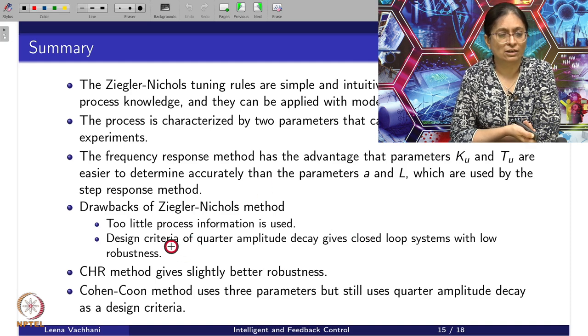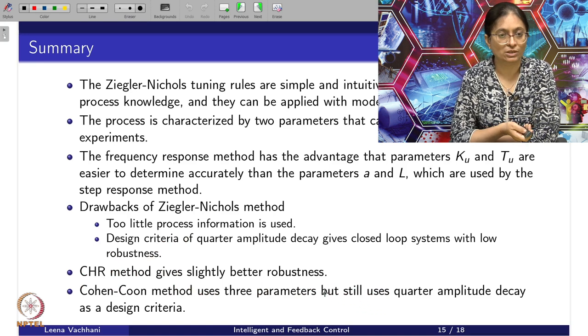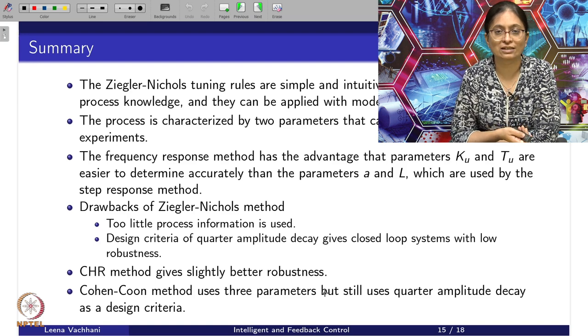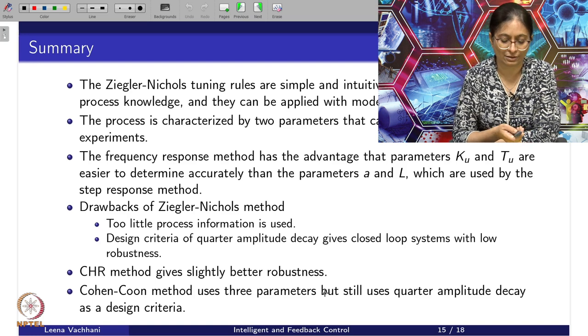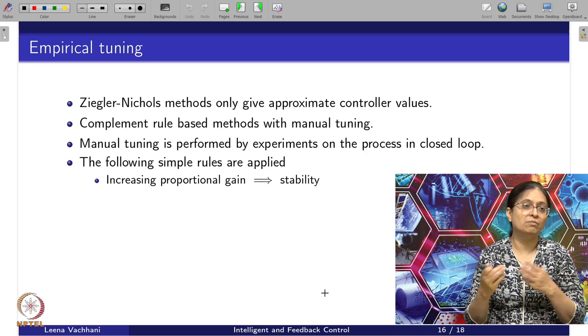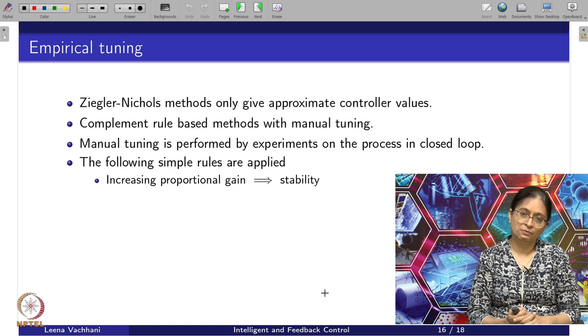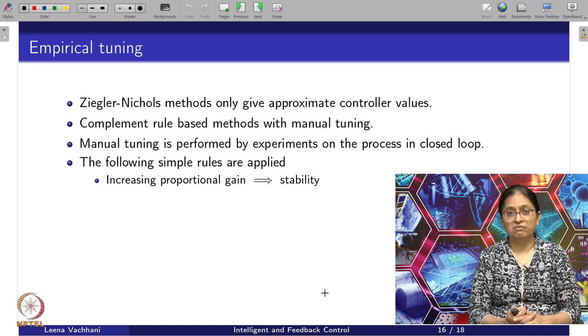Compared to ZN, the CHR method gives slightly better robustness. Cohen-Coon, since it uses three parameters and still uses quarter amplitude decay as a design criteria, provides even better robustness and load disturbance rejection compared to ZN. At the same time, ZN is a very simple and intuitive method that can be used in certain cases, especially when the process is completely a black box to us. Overall, ZN, CHR, and Cohen-Coon methods give intuitive ways to design the controller.